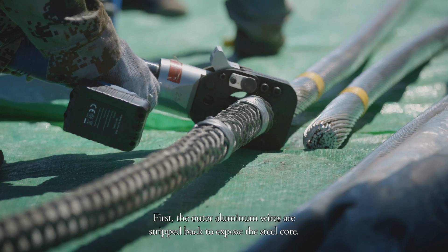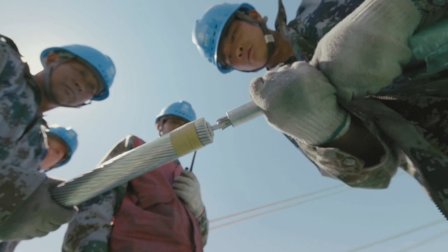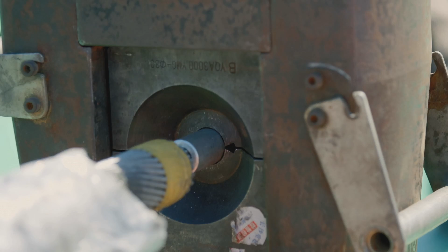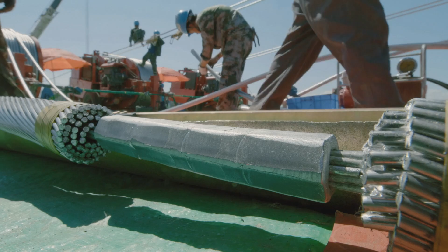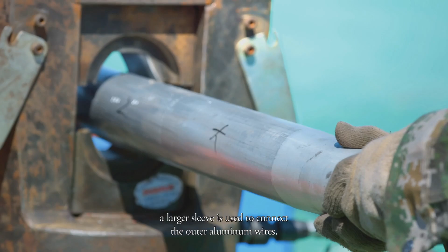The cables are connected by intense pressure. First, the outer aluminum wires are stripped back to expose the steel core. Then the two ends of the steel core are inserted into a metal sleeve. A hydraulic clamp presses hard on the sleeve to hold the two sections of steel cable firmly together. After the steel core is joined, a larger sleeve is used to connect the outer aluminum wires.